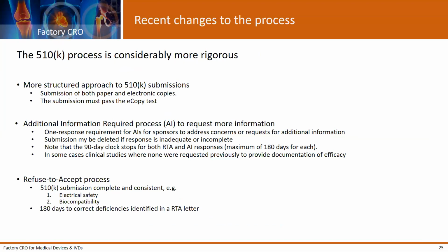There is a one response requirement for sponsors to address concerns or requests for additional information. Please note that the 90-day clock stops when there is a request from the FDA. In some cases, clinical studies are requested where they have not done so previously.